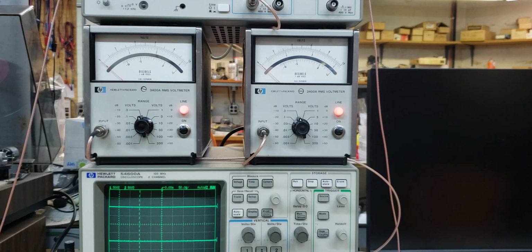So the question naturally comes up, what about low frequency calibration? Let's see how this machine does it. Let's start with 500 hertz and go down from there. This is 500, and as you can see, it's perfect. 250 hertz, perfect. It's like 0.2, 0.3 dB plus, pretty much zero or negligible. 125. Very commonly there is a small peak there, and in this case the peak is about 0.7 dB, which is negligible.